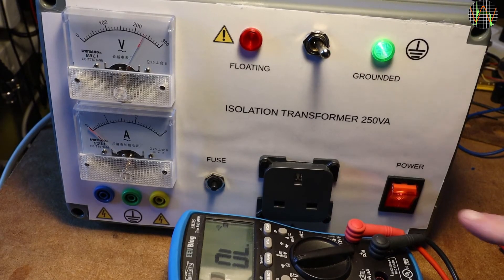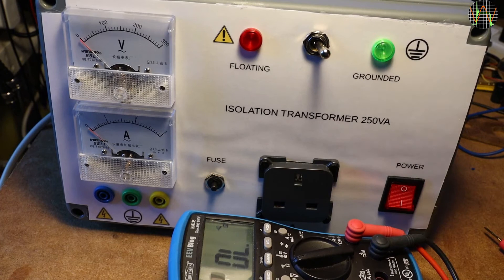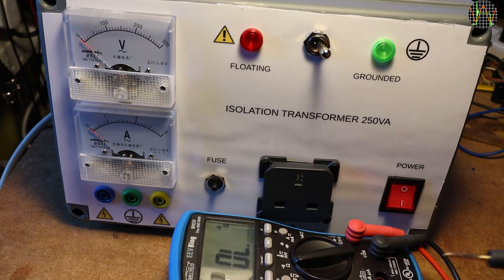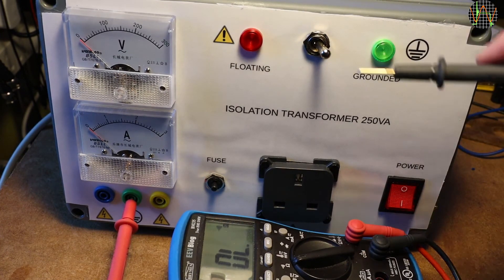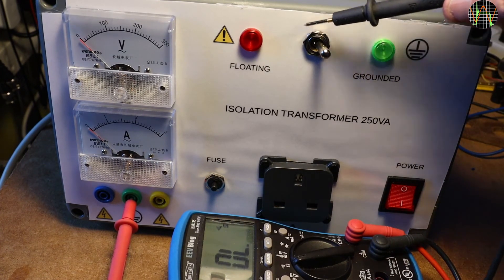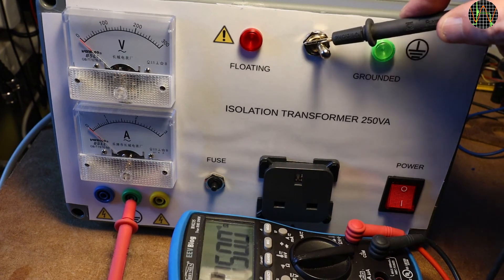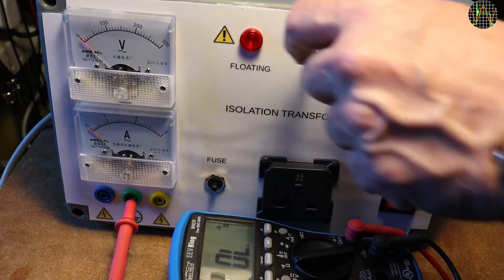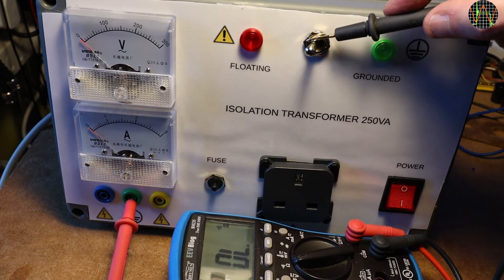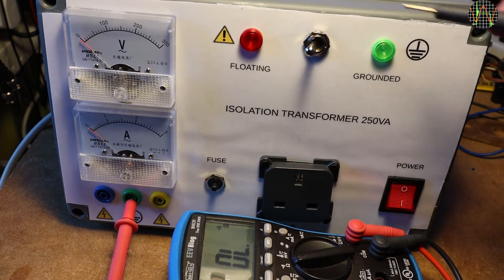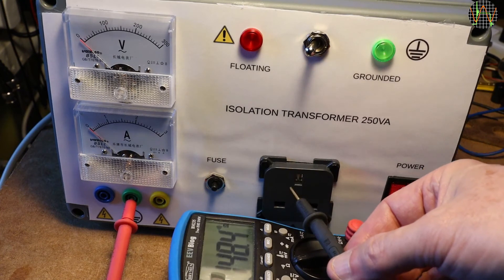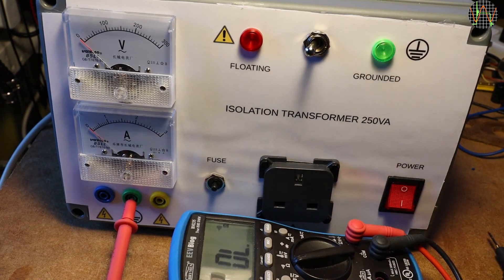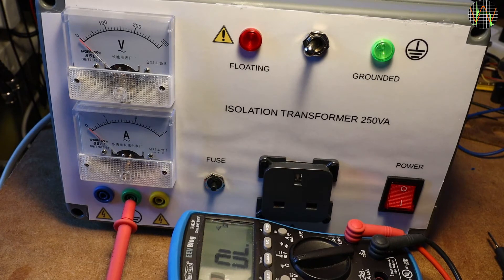Here is one way of testing the working of S2 once the unit is off, using a multimeter in continuity mode. Connecting one lead to the earth terminal and the other lead to a normal earth. In this case, I used the metal part of the switch itself. In grounded mode, there should be continuity. But in floating mode, of course not. And while doing this, it is worthwhile checking that the earth terminal is still permanently connected to the power socket ground.